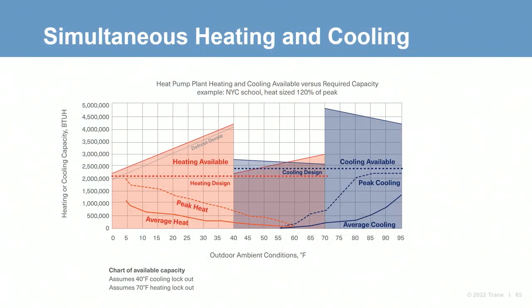Let's examine simultaneous heating and cooling. We'll go back to our New York City school example with two 200-ton heat pumps that Charlie introduced. Dividing the system capacity between two or more units provides multiple benefits. First, it provides system turndown capability, which is especially beneficial to the many operating hours at lower loads. Second, it provides adequate capacity to meet simultaneous heating and cooling loads and efficiently addresses them without the complexity of heat recovery. But what if we can take advantage of heat recovery? Maybe my building has a data closet or requires a lot of ventilation air.